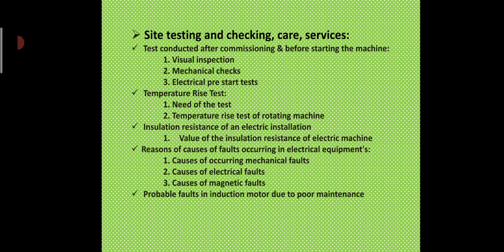Second, the causes of a broken brush holder include use for a long period, improper fitting during maintenance, more or less pressure of the spring on the brushes, use of the wrong grade of brushes, and wrong angle of brushes. Causes of loosening of the commutator bar include excessive vibrations, loosening of the mica ring, overload for long durations, etc. Causes of loosening of the armature core include unbalancing of magnetic force and overheating of the core. Fifth, the causes of bending of the shaft include excessive length of the shaft, more overhang, misalignment, and carelessness during opening and fitting the equipment.